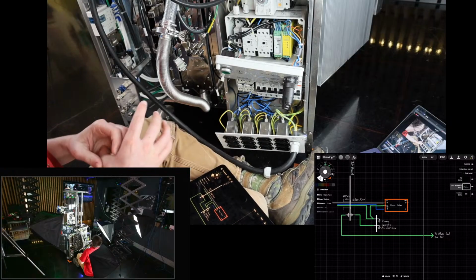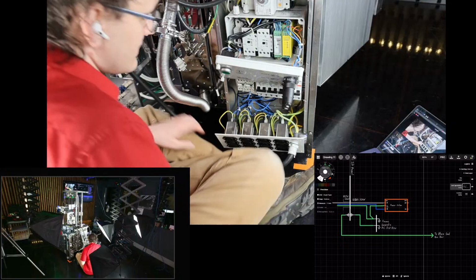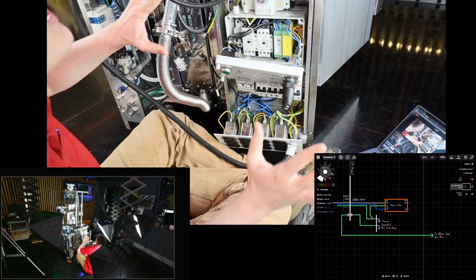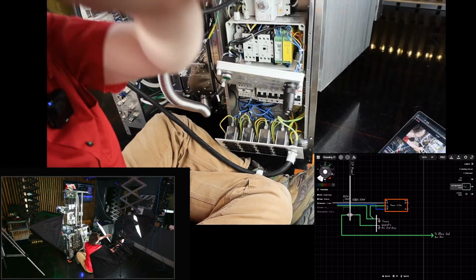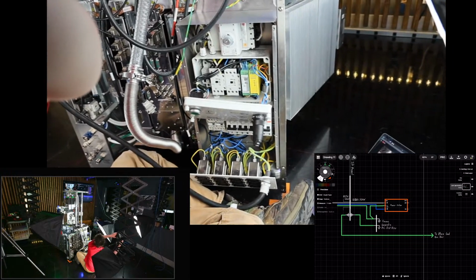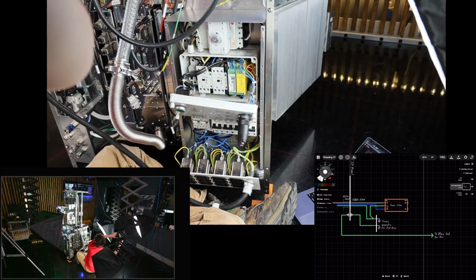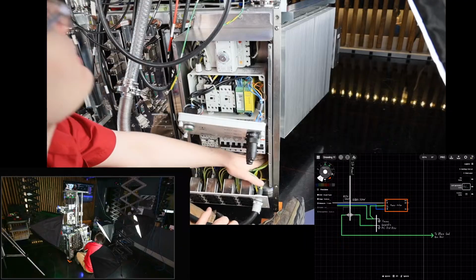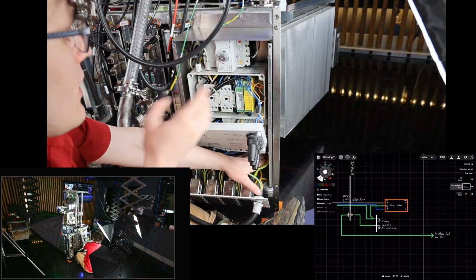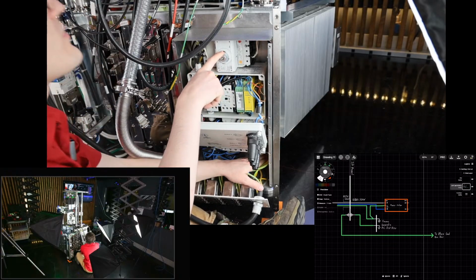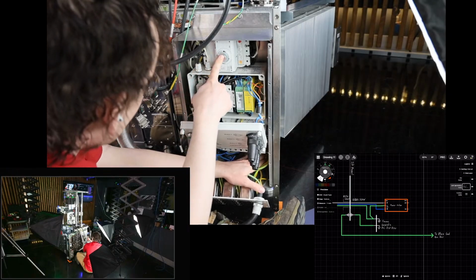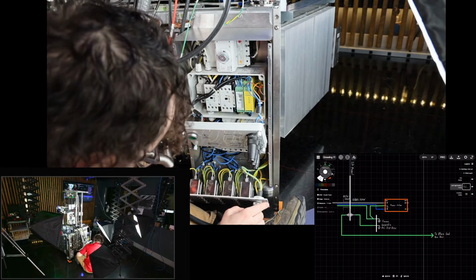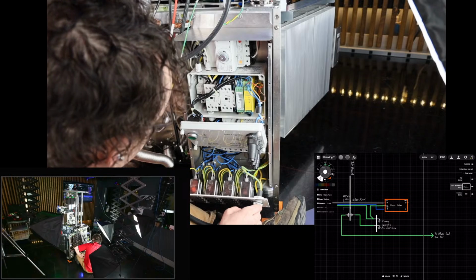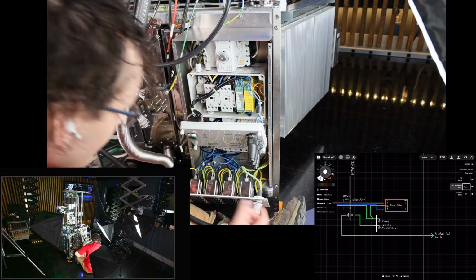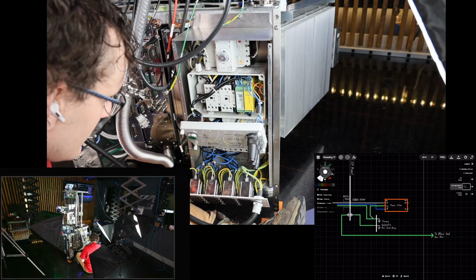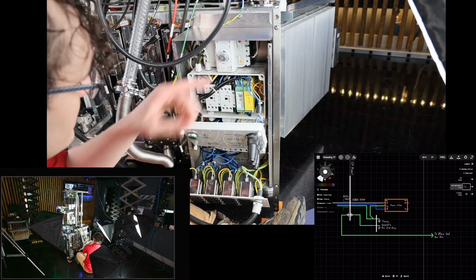So where on earth does this go after this? Now we've got to figure out what happens after our power filter. If I had to guess, just gonna take a guess here, the power filter's down here. I'd be shocked if the power filter went anywhere else but the main disconnect up here. Why wouldn't you put the filter after the main disconnect? Power filters fail. They smoke. They have issues. So why wouldn't you put the filter after the disconnect?